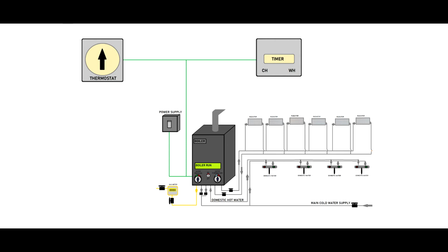However, most of the timers come with that function too, which is used for system boilers. With this new system in place, it's not enough just to enable the boiler. You really have to have a demand from the thermostat and from the timer. This is how it works when you use a timer and the room thermostat. However, to use the hot water, it's enough to turn on the tap, because the boiler has a system inside which will sense that domestic water is needed, and it will enable the hot water system.